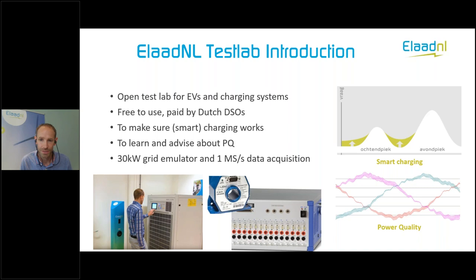We have a lab at ElaadNL offices in Arnhem. We have a grid emulator of 30 kilowatts, so we can create our own electricity grid — clean grid, but also a distorted grid — to see how a vehicle or DC charger is immune to power quality effects. We have measurement devices that can measure up to one mega sample per second, so we can see all current and voltages in high detail and detect any disturbances that occur during charging.